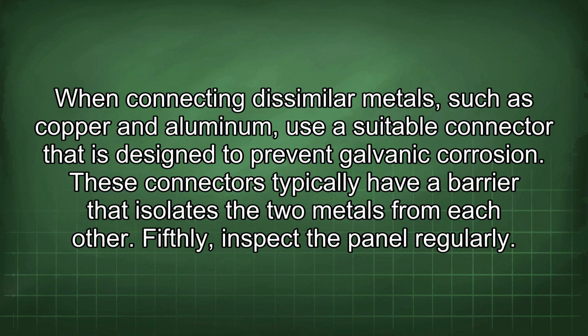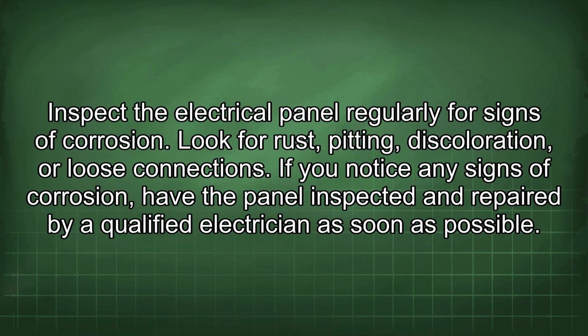Fifthly, inspect the panel regularly. Inspect the electrical panel regularly for signs of corrosion. Look for rust, pitting, discoloration, or loose connections. If you notice any signs of corrosion, have the panel inspected and repaired by a qualified electrician as soon as possible.